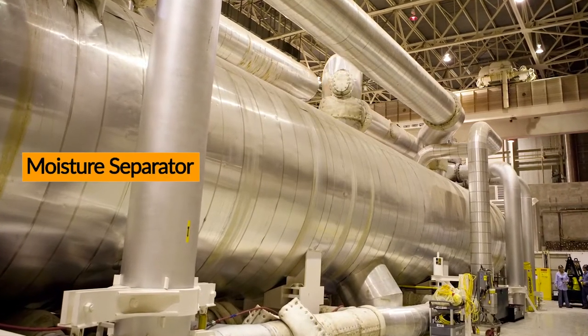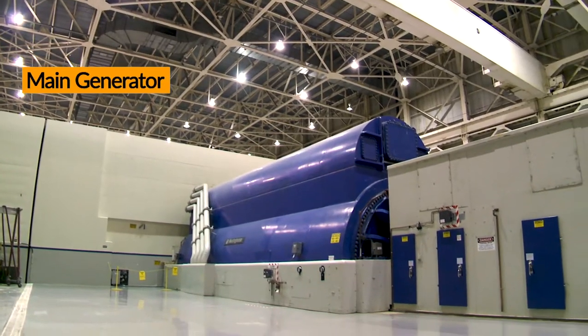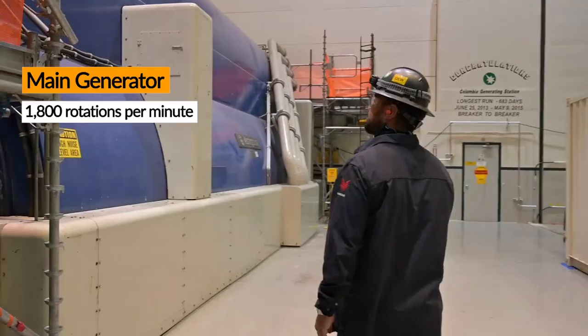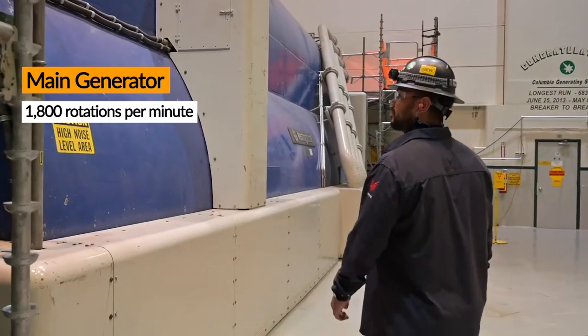After the steam leaves the reactor vessel, a series of moisture separators purify the steam and it gets channeled to four large turbines attached to the main generator: one high pressure turbine and three low pressure turbines, all attached to a single shaft. The main generator converts the mechanical energy of the turbine into electricity, producing about 1,207 megawatts electric.